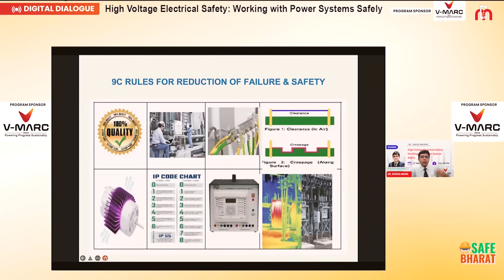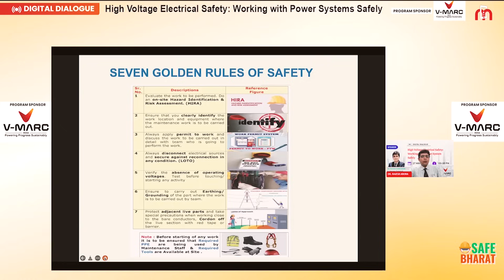When you are working with any equipment, these are the 7 golden rules of safety. You have to do the HIRA, identify the hazard, and do the risk assessment. You have to clearly identify where you are going to work, apply for the permit to work, do the LOTO, and ensure that where you are going to work is free of operating voltage. You have to do proper temporary earthing before starting any maintenance activity, ensure there is no adjacent live part, and before starting any work, ensure that the required personal protective equipment is being used by maintenance staff and the required tools are available at site.